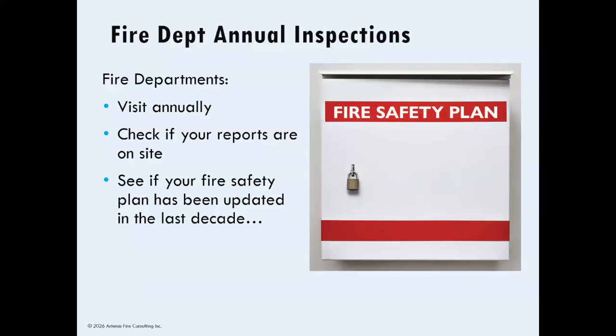As well as your annual service provider, you will have your annual visit from the fire department in your municipality. Their visit may be minimal or in-depth, depending on the district, and the report may or may not ask that additional testing or work be undertaken on site. Most do at least a cursory check on the building to make sure that the annual inspection report by the service provider has been completed and that the reports are on site.